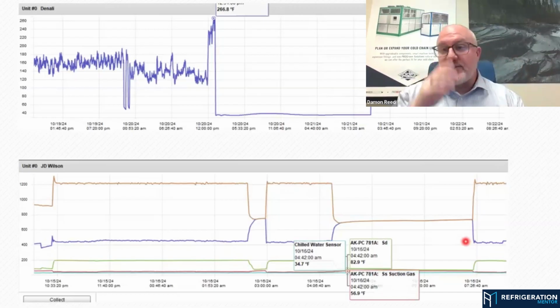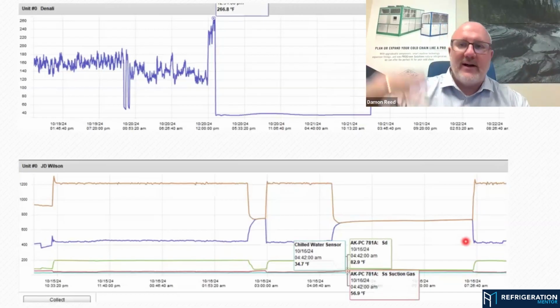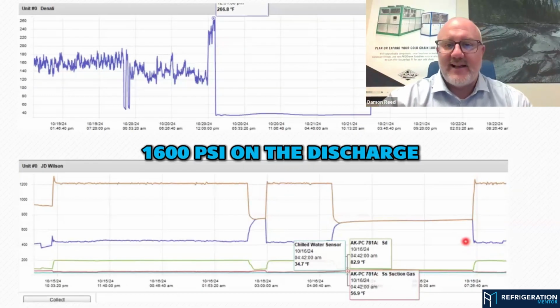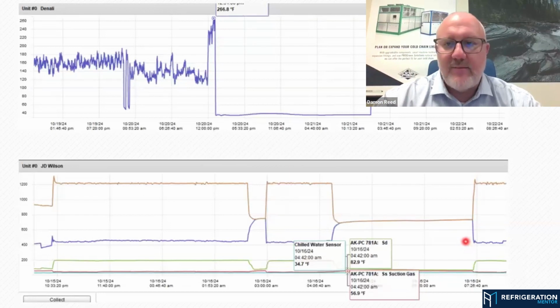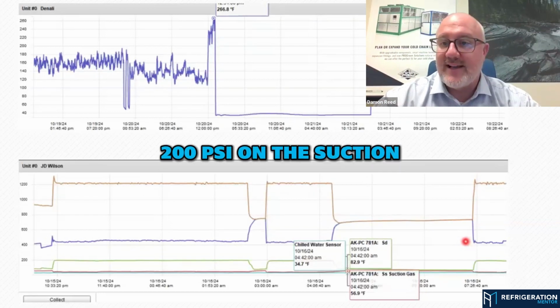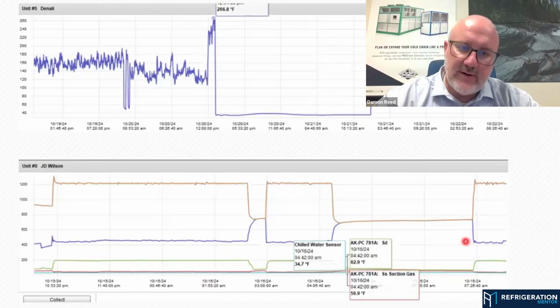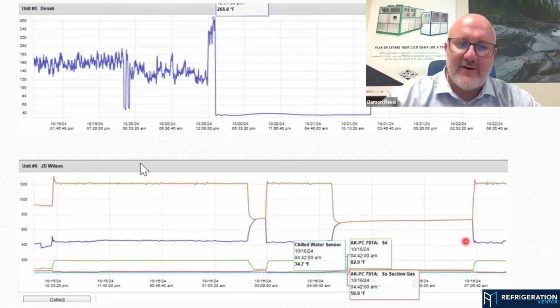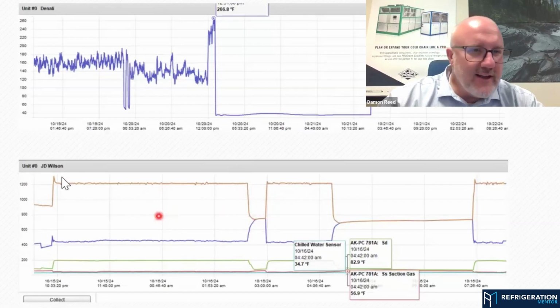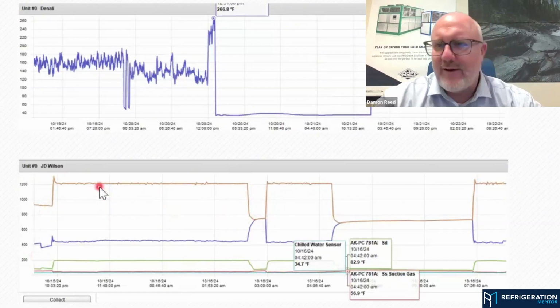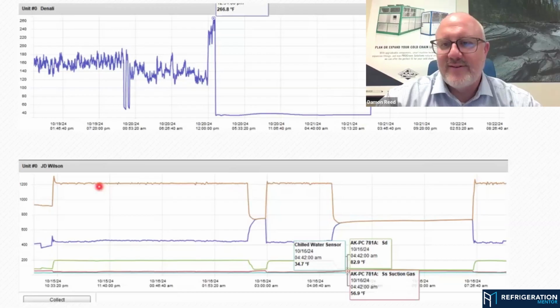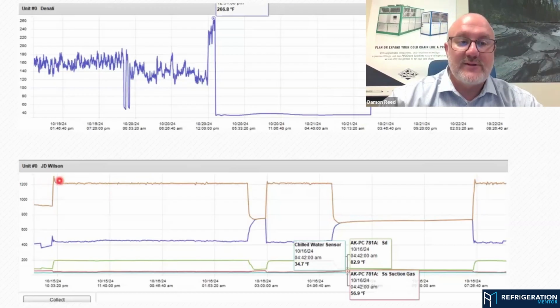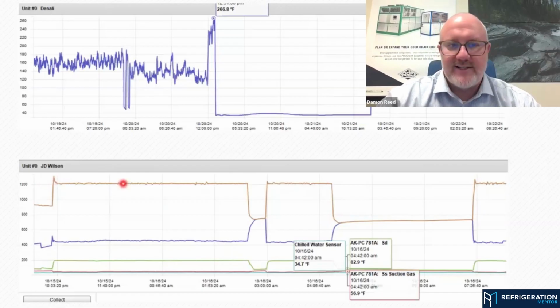Well, we know when that trips, we either went above 1600 psi on the discharge, or we went below 200 psi on the suction. And we're looking at things and we're like, here we're operating, and then we trip. Well, I can't see off to the side, but I think we were like 1300 psi. We're well away from 1600. The condition was present. It was reset manually on site.